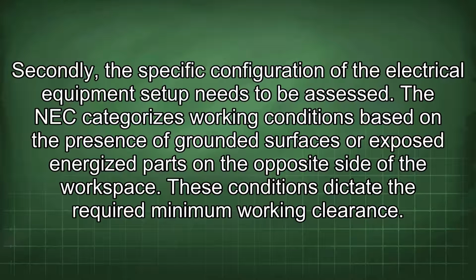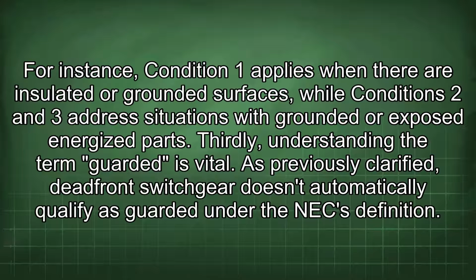Secondly, the specific configuration of the electrical equipment setup needs to be assessed. The NEC categorizes working conditions based on the presence of grounded surfaces or exposed energized parts on the opposite side of the workspace. These conditions dictate the required minimum working clearance. For instance, Condition 1 applies when there are insulated or grounded surfaces, while Conditions 2 and 3 address situations with grounded or exposed energized parts.